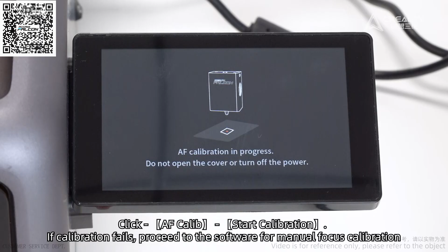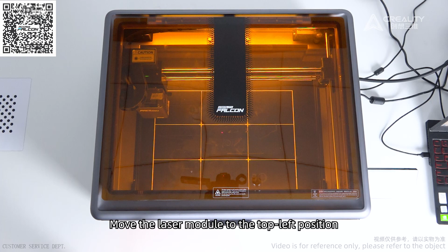Click AF Calib. Start calibration. If calibration fails, proceed to the software for manual focus calibration. Move the laser module to the top left position. Open the software and click Settings at the bottom right. Click Start calibration.